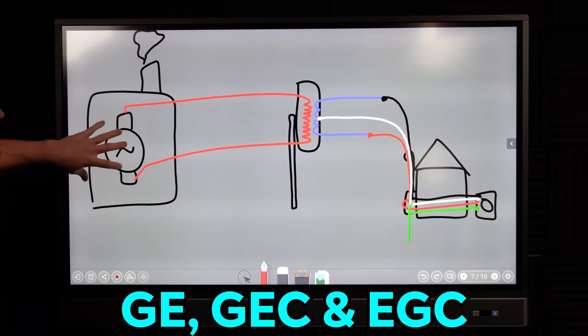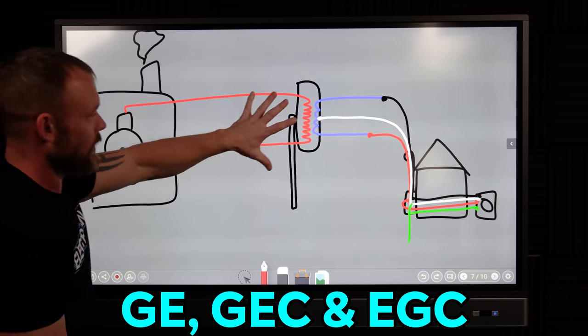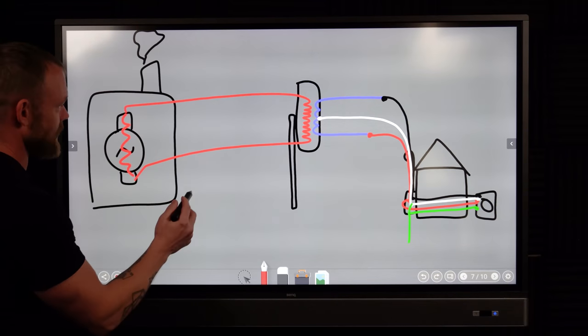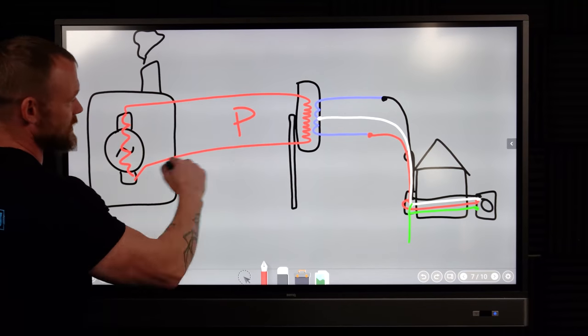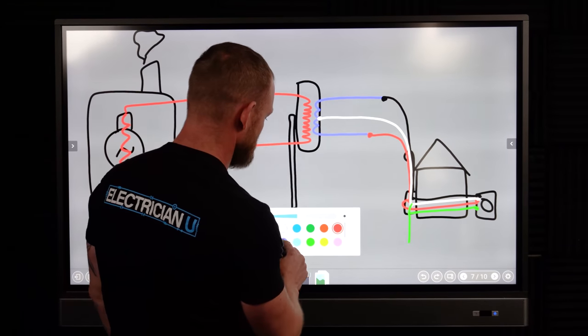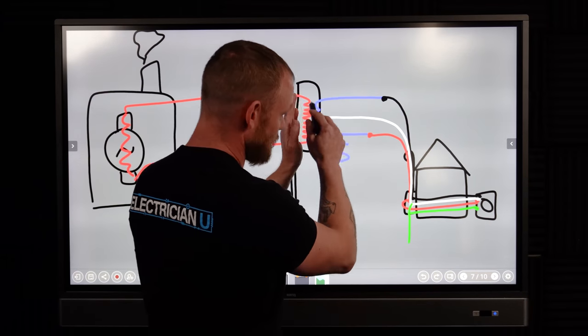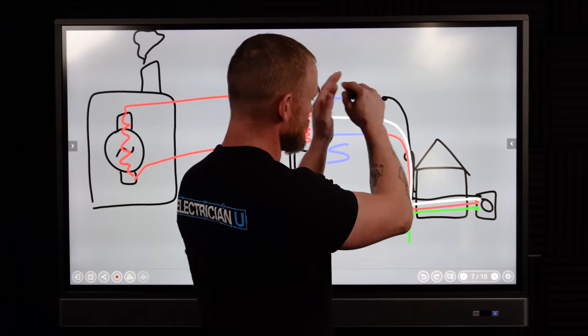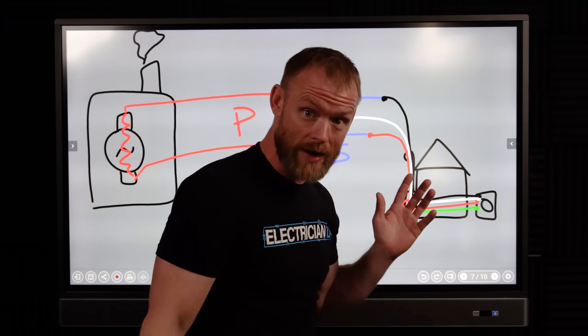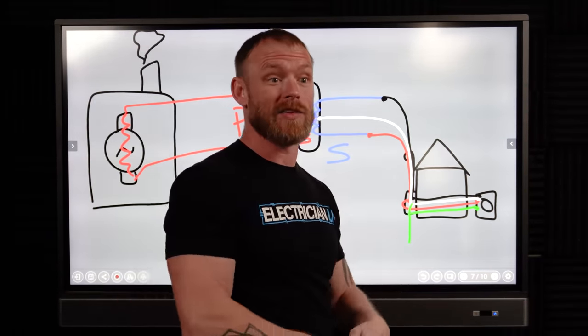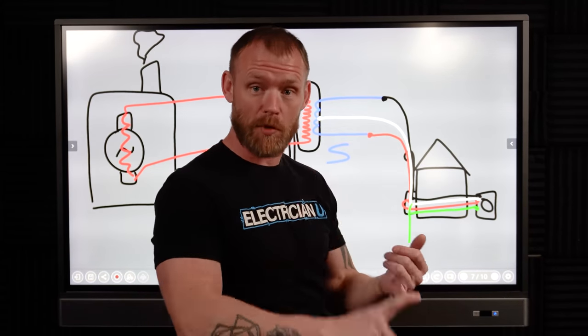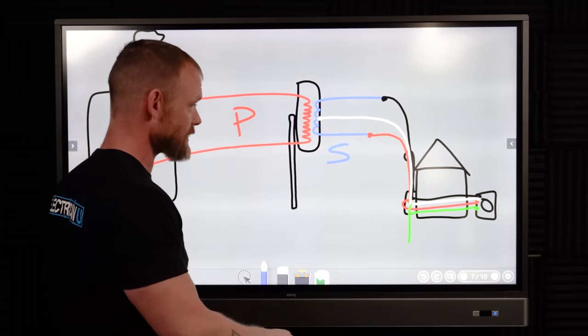Looking more closely: we have an industrial generator, a transformer on a pole, and a house. On the primary side we have one complete circuit; on the secondary side we have a complete circuit from the transformer through the equipment and back. Current only travels if there is a completed loop, and the only way to stop current is by opening the circuit — that's why we have breakers, switches, and disconnects.